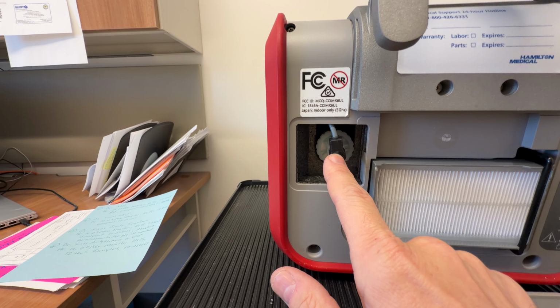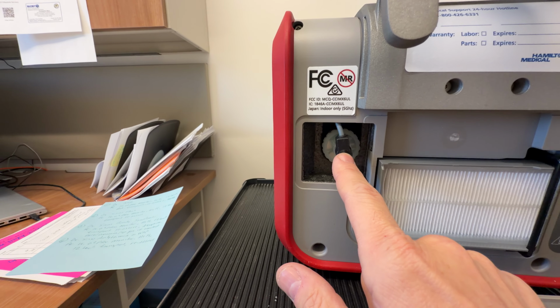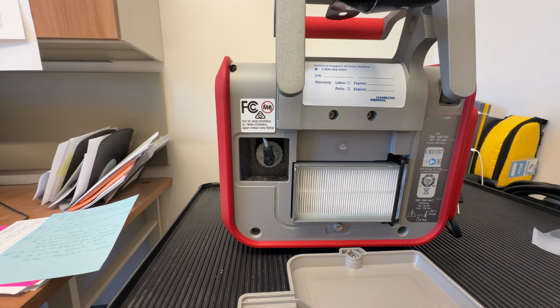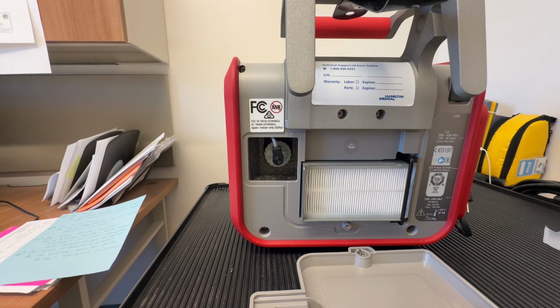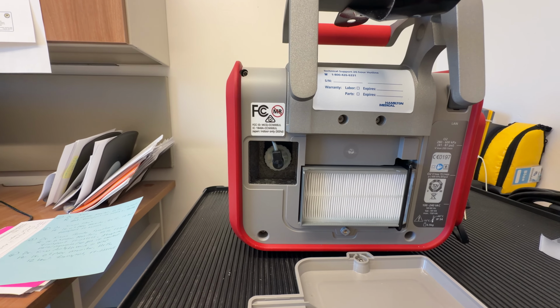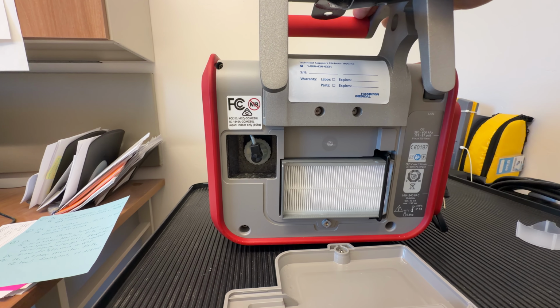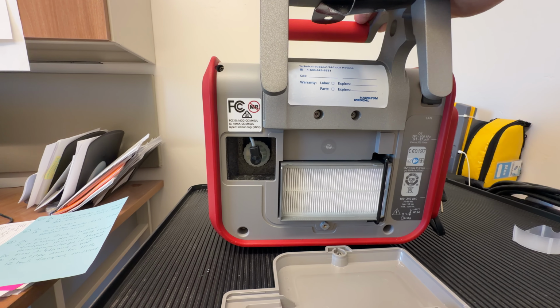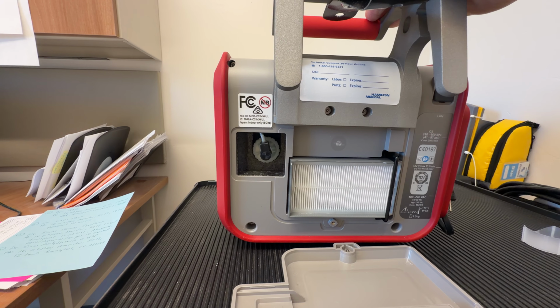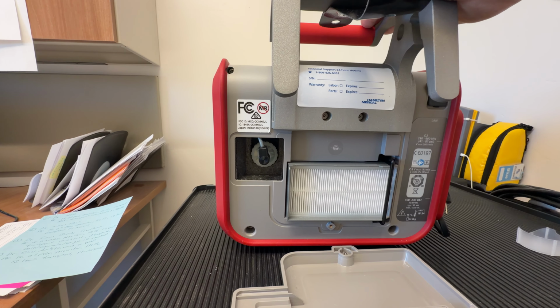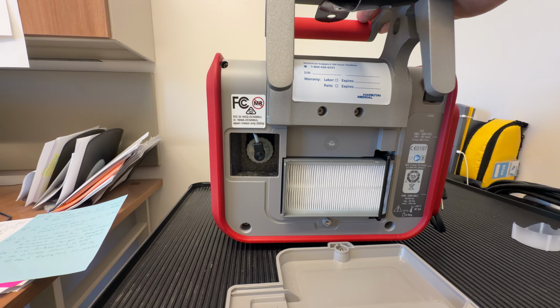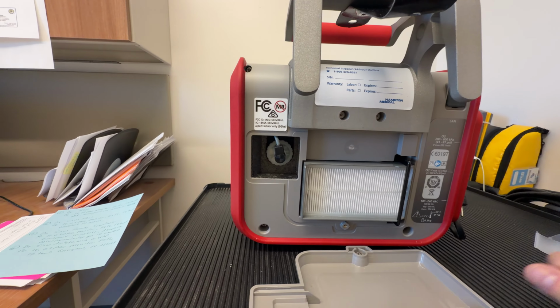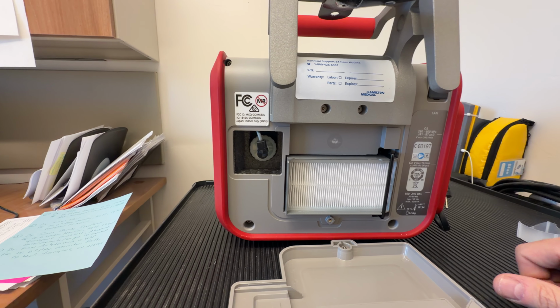I talked to IT about this, and if you are just using this ventilator in a kind of a training environment like we are here, primarily on room air, you can expect about 1 to 2 years of use out of your oxygen sensor. Remember, your oxygen sensors have an anode and a cathode, and ions accumulate there, and so they do go bad over time and need to be replaced. However, if you are using this as a transport ventilator, or you're using this in a clinical context on actual patients that are receiving various FiO2s that are above room air, above 0.21, you're going to have higher concentrations of oxygen, and that sensor will go bad, quote unquote, faster, and so you may need to change that.